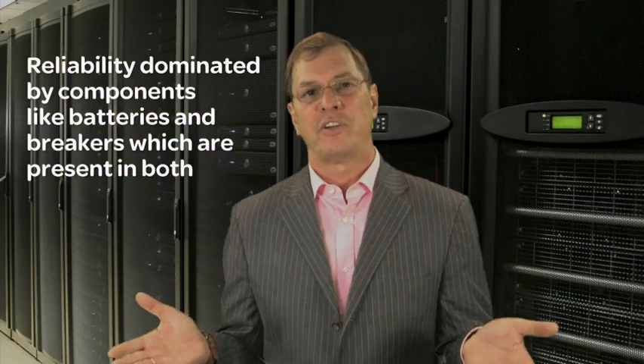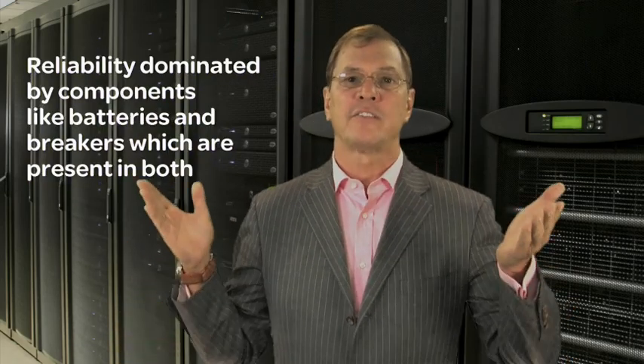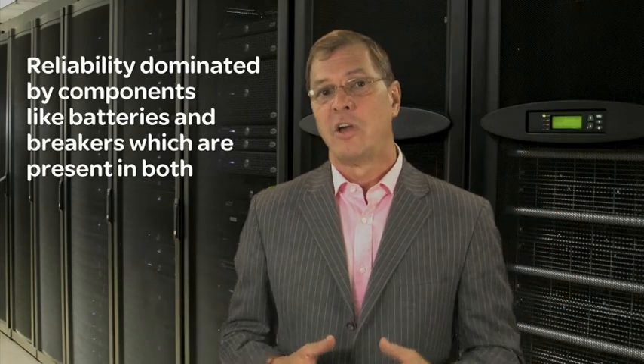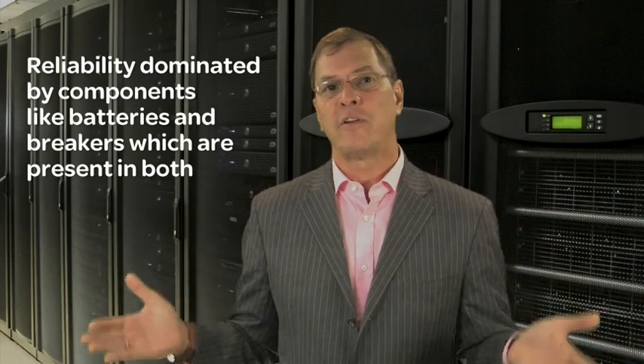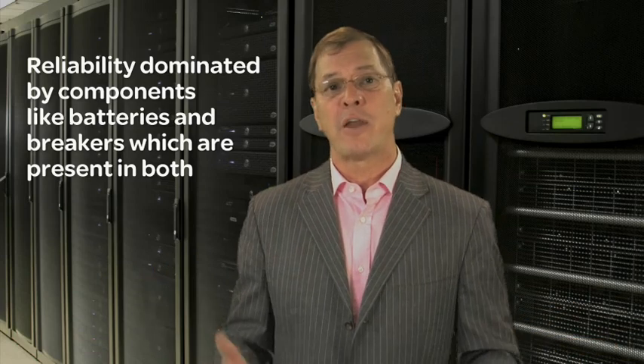But a DC system cannot have that option because the output DC is incompatible with the input AC, so no bypass is possible. So overall, the reliability of both systems is really dominated by devices like batteries and circuit breakers, which have the same reliability whether used in an AC or DC system and are present in both. For example, if I've got an AC UPS or a DC UPS, they both have the same battery. And if the battery is dominating the reliability of the system, it really doesn't matter whether it's AC or DC.